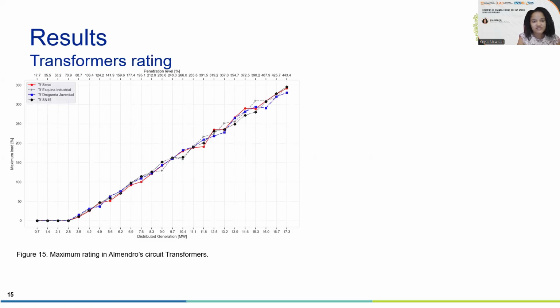The third performance index is transformers rating. In this case, it is the most limiting factor for the integration of renewable energy in the grid of San Andres Island, and the limit, or the hosting capacity, is found at 5.5 megawatts. That is double the load connected to the circuit. So this is the hosting capacity found for the grid of San Andres Island under this methodology.